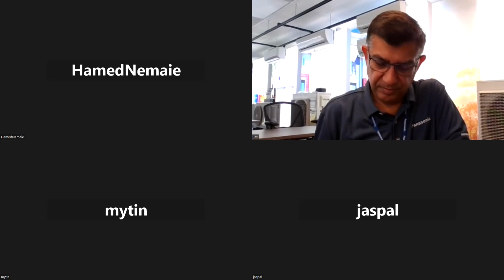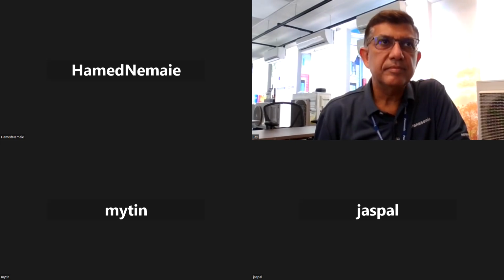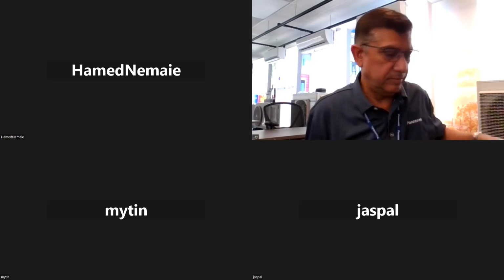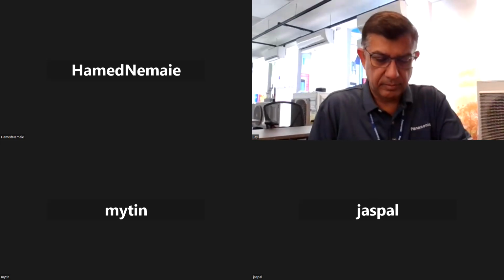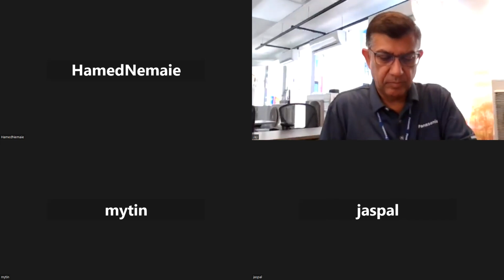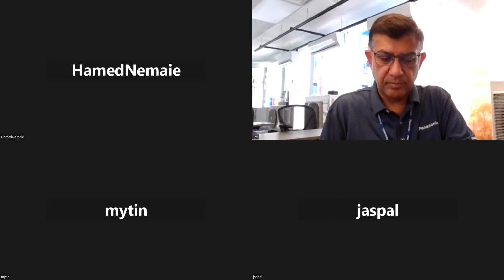Okay, but I was just saying, because I noticed we'll say it can run to a certain point, but a lot of times it falls a little bit short. Like I have a friend in Minden, Ontario. It gets very cold up north, and the guy is using a 5-zone multi-zone, and he's using it throughout the year, simply because for the past 3-4 years now, our winters are not that severe. So if your customer is looking for actual data, everything is available in our service manual. But again, keep in mind, the lower the temperature, the lower the capacity.